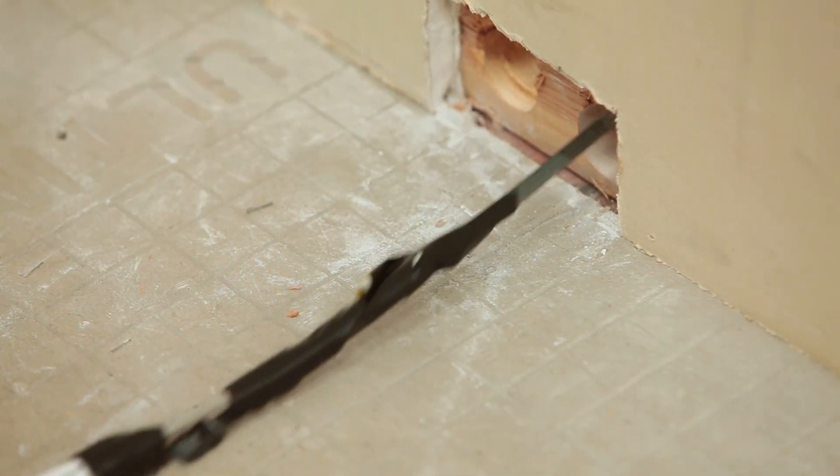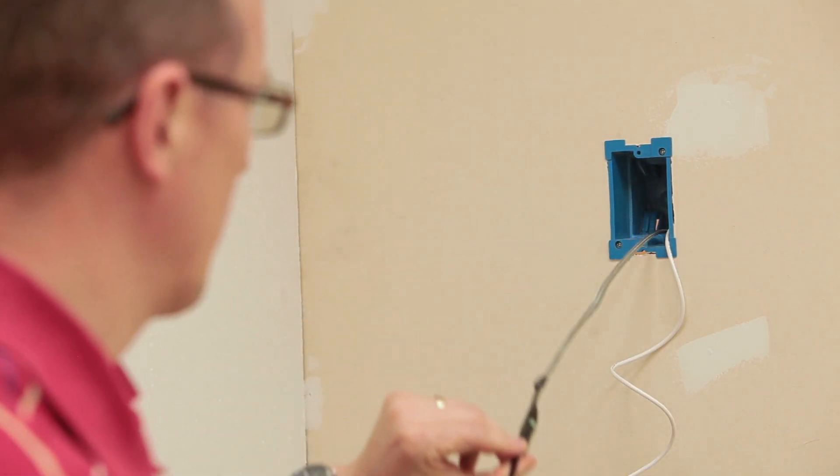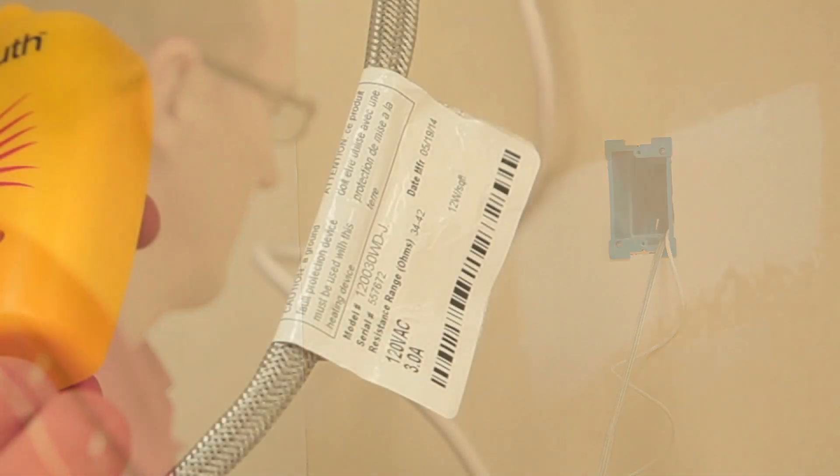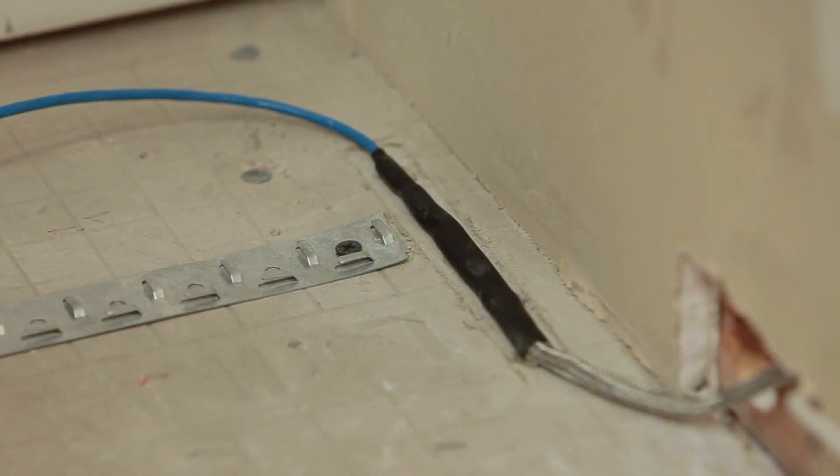Begin installing warm wire by feeding the power leads and sensor wire up to the control or junction box location. Do not remove the label attached to the lead. Take care not to pull the factory splice into the wall when pulling leads into the electrical box. This splice must be embedded in mortar and cannot be bent.